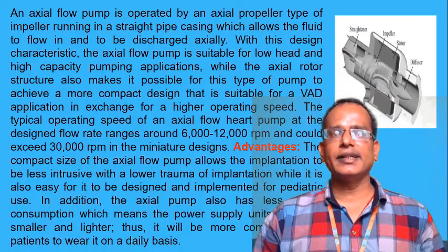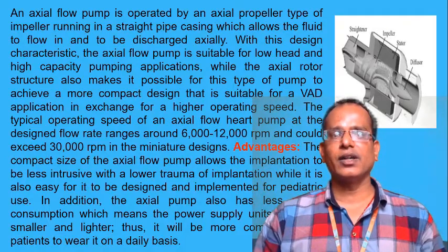With this design characteristic, the axial flow pump is suitable for low head and high capacity pumping applications, while the axial rotor structure also makes it possible for this type of pump to achieve a more compact design suitable for implantable application in exchange for a higher operating speed.